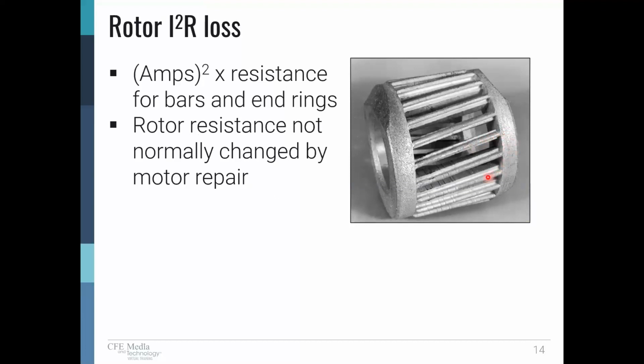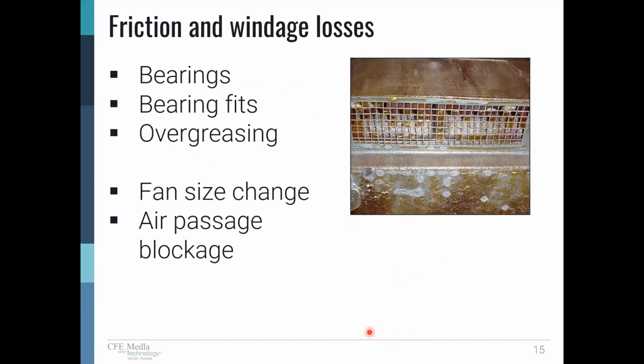So we have the different resistances and so forth, but we've got that. We've got these bars and end rings going through. And in terms of the repair, the rotor itself, unless there was a catastrophic repair, there wouldn't even be a call to change anything in the rotor. It just stays the way it is. It's not disturbed. And if there was a significant failure where the rotor, let's say, rubbed the stator core, for most motors, the vast majority, it wouldn't be economical to try and repair the rotor. Probably what would happen is either the rotor is going to be replaced or a new rotor is going to be delaminated and relaminated with new bars and end rings. So again, rotor repair does not normally change rotor characteristics, and the rotor itself is not normally changed during repair.